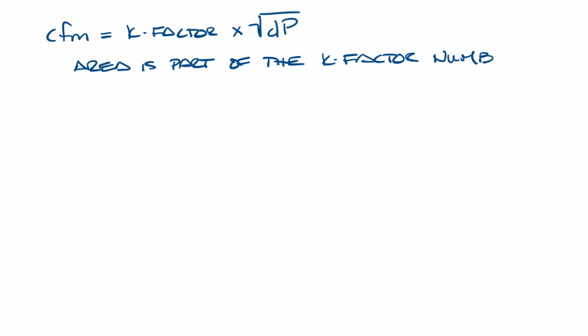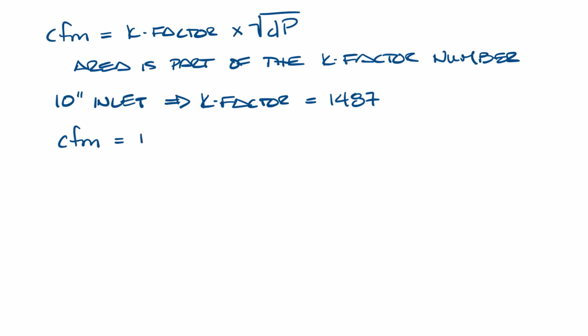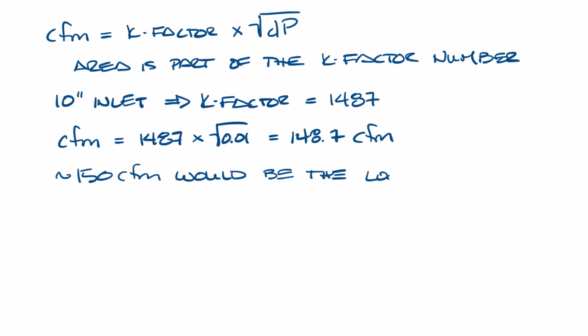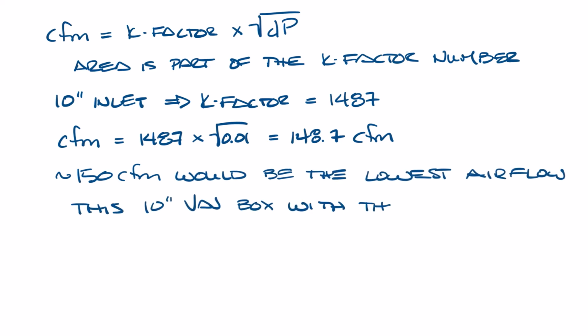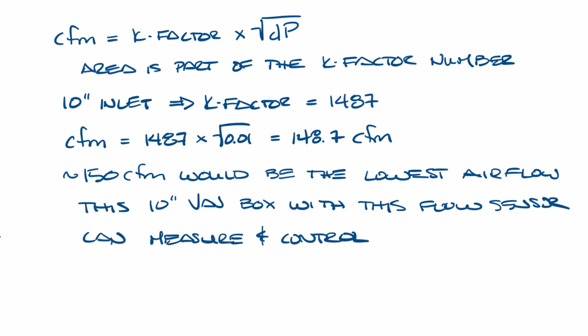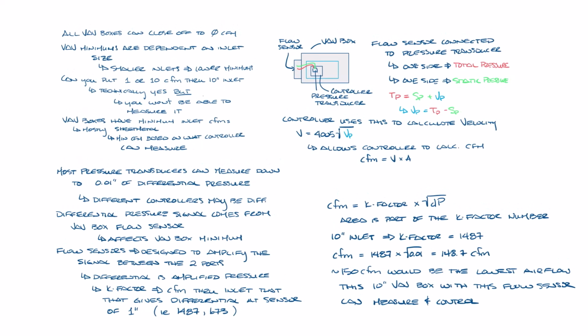So the equation to calculate CFM from the flow sensor signal is CFM equals K factor times the square root of the differential pressure. And notice that inlet area isn't in the equation because that's part of the K factor number. So let's say these are 10-inch flow sensors, and the K factor for this VAV box with this particular sensor is 1487. So the CFM equals 1487 times the square root of 0.01 inches. That equals 148.7 CFM. So about 150 CFM would be the lowest that this 10-inch VAV box with this flow sensor in it could measure and control effectively. So let's bring all of this back on screen. That's how you determine the VAV box minimum inlet CFM.